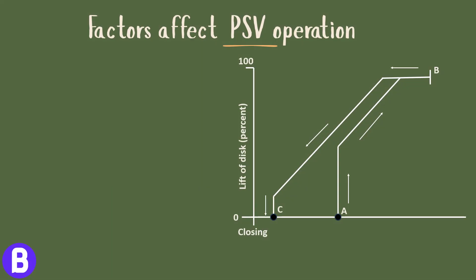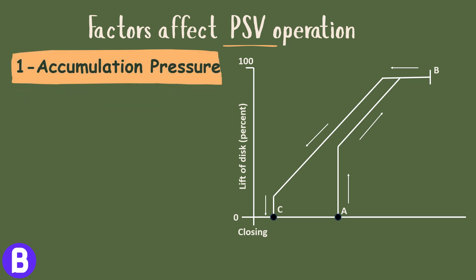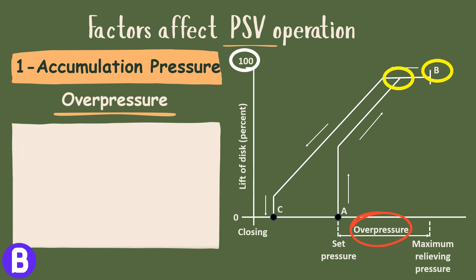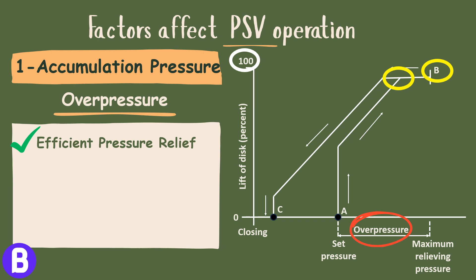Let's talk about some parameters that shall affect the pressure safety valve operation. Factor 1: Accumulation Pressure. Accumulation pressure, also known as overpressure, is the maximum pressure that may build up above the set pressure of the valve during discharge before the valve reaches full lift. It is imperative for the PSV to achieve full lift within the accumulation limit to ensure efficient pressure relief without damaging the valve or the system. Exceeding this limit can lead to the valve not opening sufficiently, failing to relieve enough pressure, which may cause system failure.